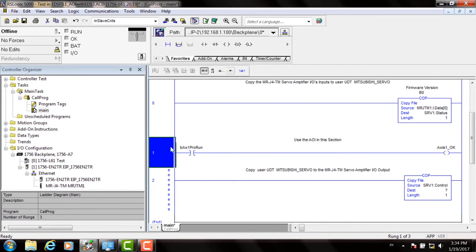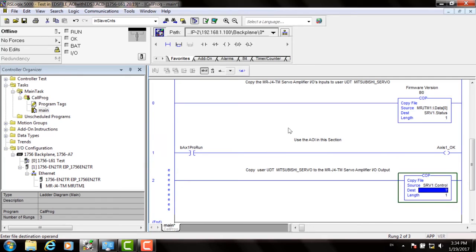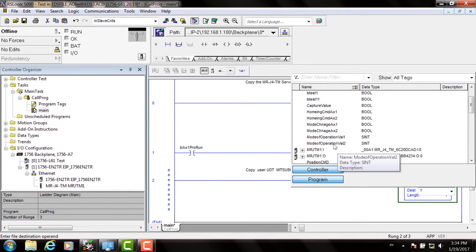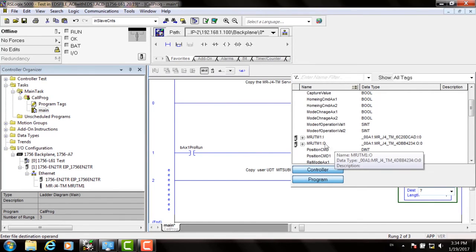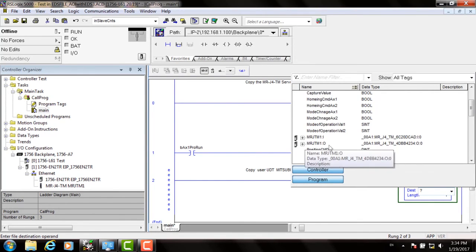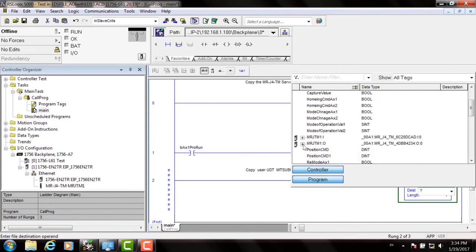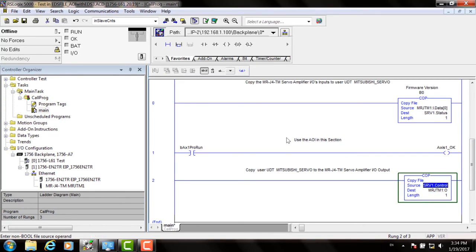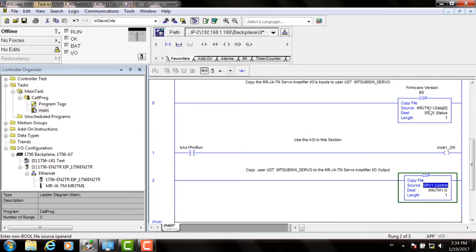And we have to do the same again on the copy instruction. This is going to copy to the servo drive. So again click on Destination. Start typing your servo drive name or choose it from the list. And this time choose the drive name colon O. The length should be 1. Repeat this procedure for any other servo drives in your system and your configuration is complete.